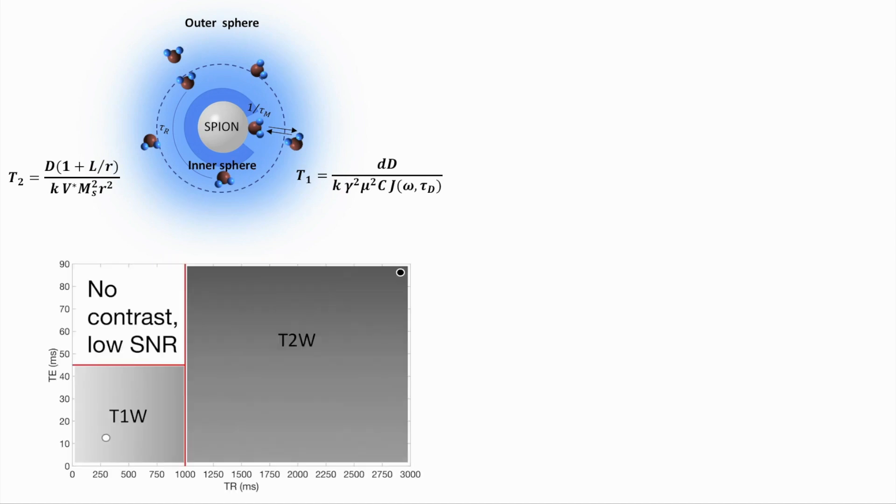A relaxometric map derived from the fast spin-echo MR phantom images at different echo times and repetition times demonstrates that positive contrast, white-gray shaded area, can be achieved at short echo times up to 40 ms with repetition time up to 1000 ms. Negative contrast, dark gray area, can be achieved at high echo times up to 90 ms with a repetition time up to 3000 ms.